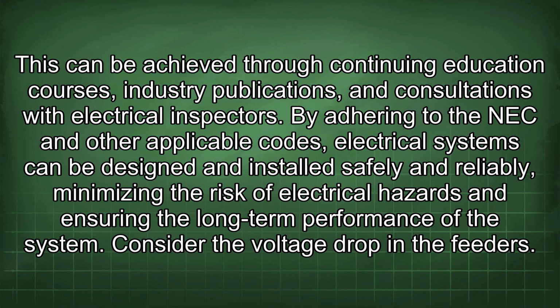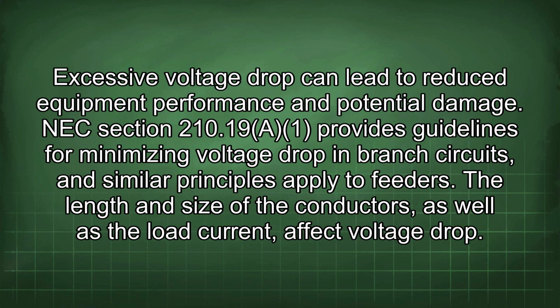Consider the voltage drop in the feeders. Excessive voltage drop can lead to reduced equipment performance and potential damage. NEC Section 210.19 provides guidelines for minimizing voltage drop in branch circuits, and similar principles apply to feeders.